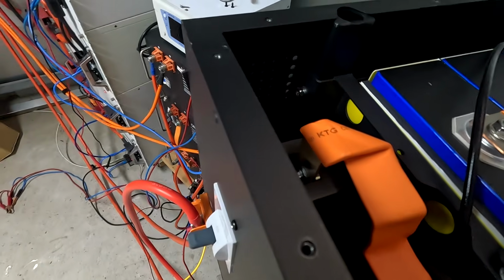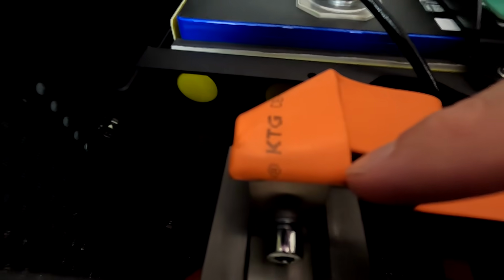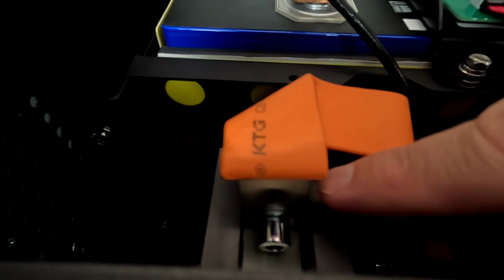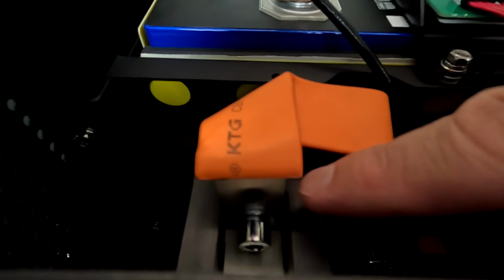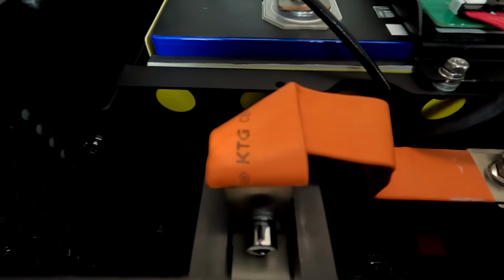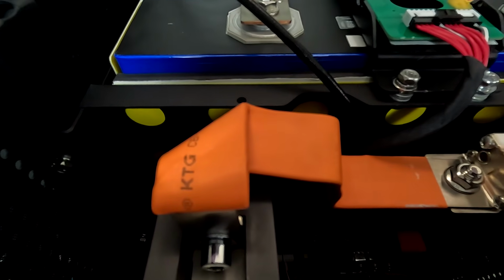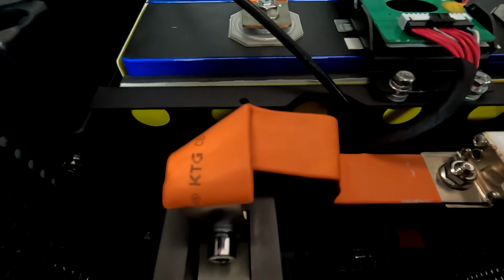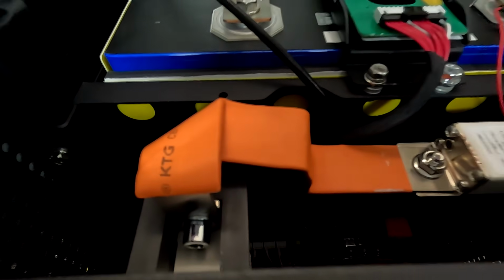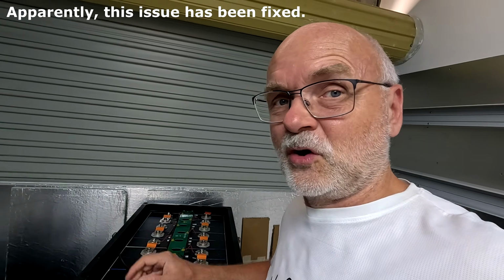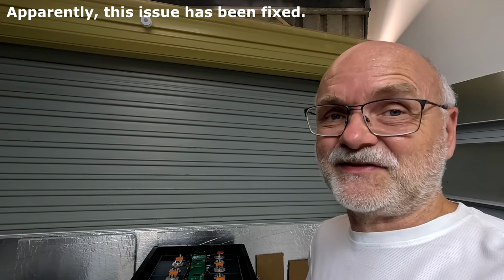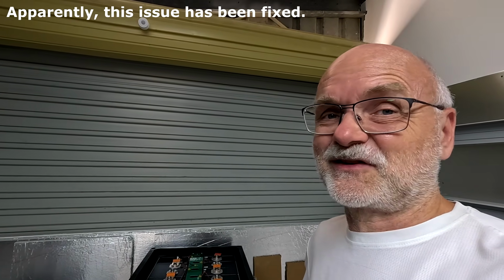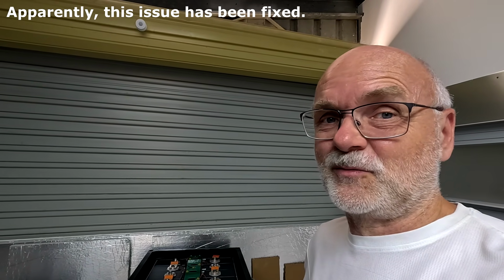This is because, if you remember the last video, I've shown you especially these two bus bars. What they did, they just cut away a bit of the bus bar, making the conductor smaller. So, now here at 100 amps we can already see and feel it, definitely feel it, that this causes a hotspot in this front section. Back then I've already reported this to them and they're working on a solution. They have to somehow keep the same diameter of this bus bar, they cannot just cut away a little bit to make it fit into the circuit breaker.